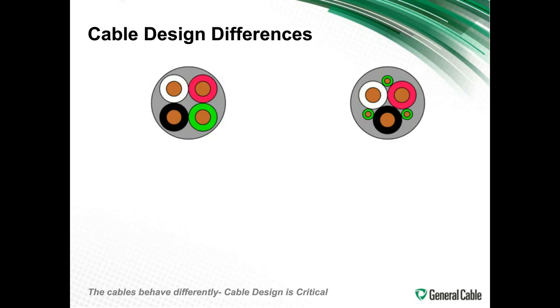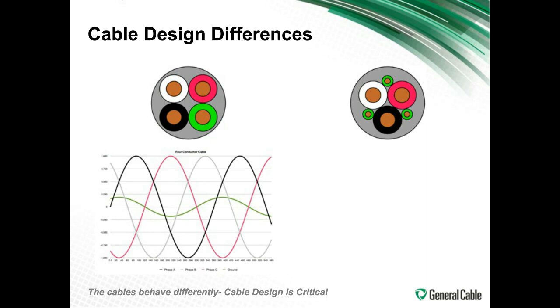Another thing to consider, because cable design is so important in this, is that the difference in design makes a key difference in the way the cables behave. If you look at this on the left, you see three conductors and one single ground. Let's look at the way the voltage behaves with the three different phases. You see the voltage, the green, actually has a slight waveform to it. That shows that there is a voltage potential created by the cable itself.